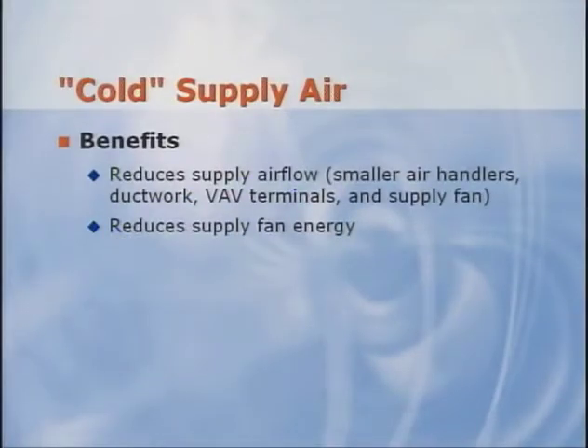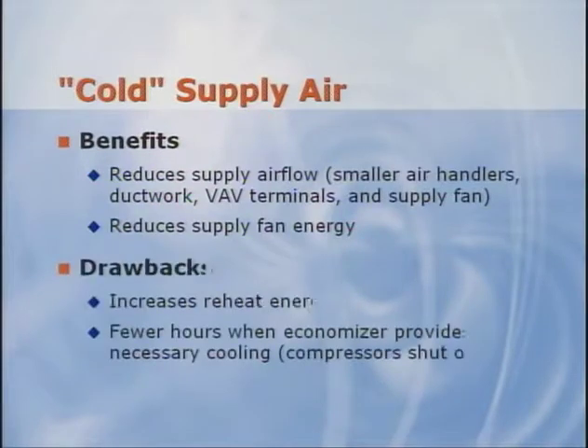Now for 3 of the systems we discussed today, cold air distribution was used in some of the locations. The appeal of cold air lies in the corresponding reduction in supply airflow. This can significantly reduce fan energy use and can also result in smaller fans, air handlers, ductwork, and VAV terminals. But supplying air at a colder temperature can increase reheat energy and result in fewer hours when the airside economizer can provide all the necessary cooling. These impacts partially offset the fan energy savings.